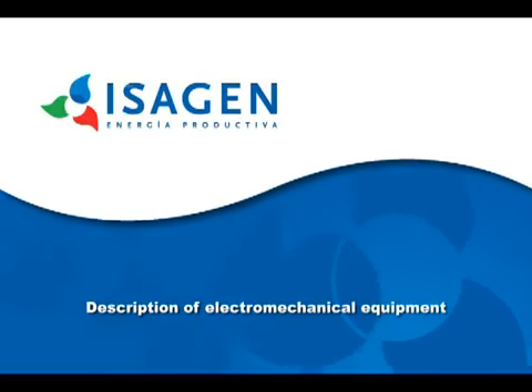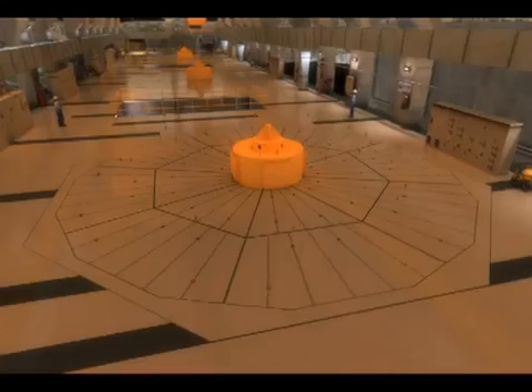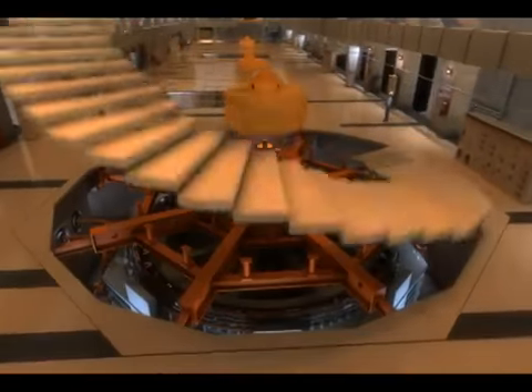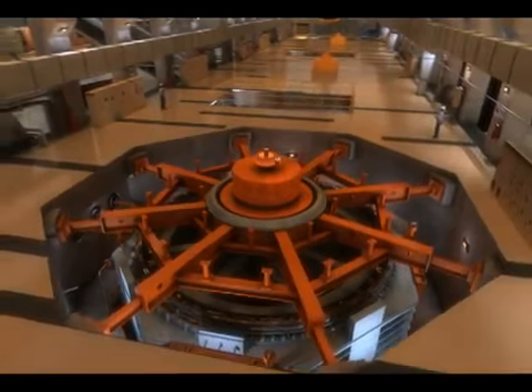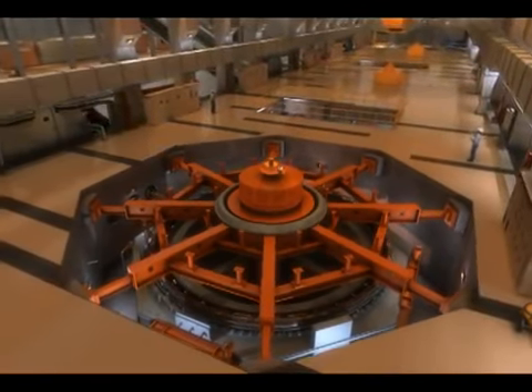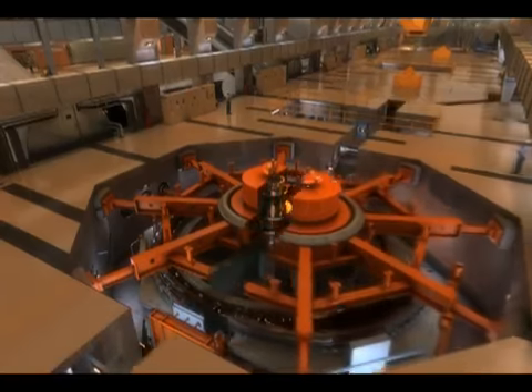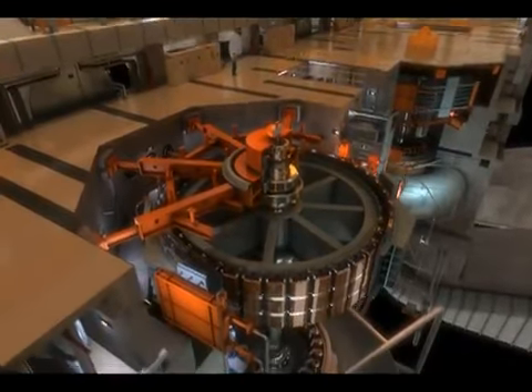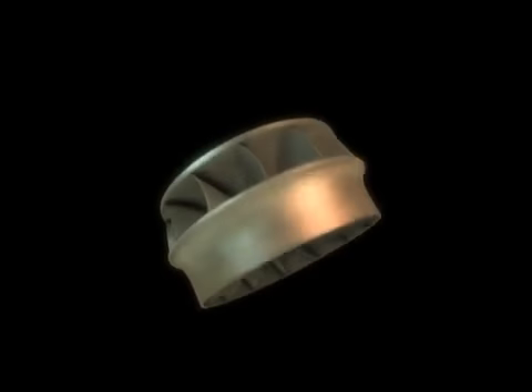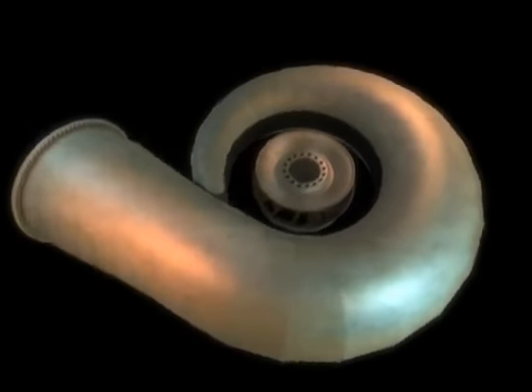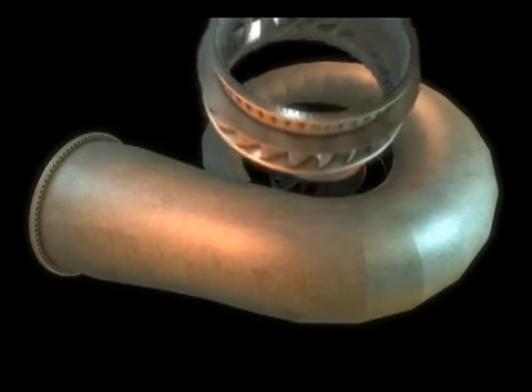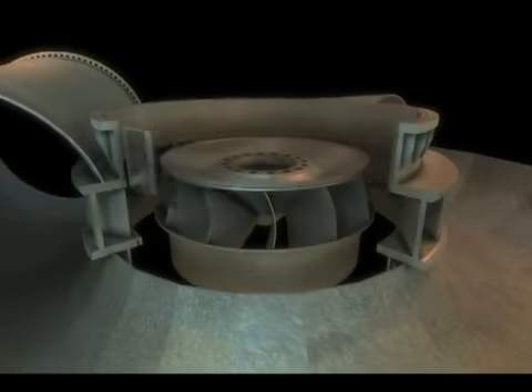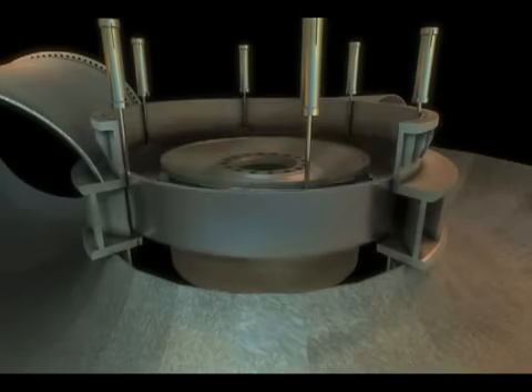Description of electromechanical equipment. The generation process that takes place in the underground power station converts mechanical energy to electrical energy. This conversion process is accomplished through a series of devices, the most important of which are the turbine and generator. The vertical shaft Francis turbine is made up of several components. A spiral-shaped scroll case that enables the uniform flow of pressurized water around the distributor. The cylindrical valve that can cut off the water flow into the turbine.